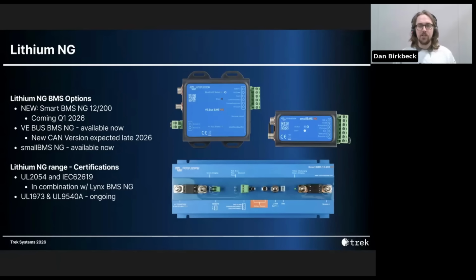The VE.Bus BMS NG and smallBMS NG are available now, with a VE.Bus BMS NG CAN version expected later this year. On the certification side, Victron has achieved both UL 2054 and IEC 62619 certifications for lithium NG batteries when paired with a Lynx BMS NG. The UL 2054 specifically evaluates the battery pack, including its casing and protective circuitry, to reduce the risk of fire or explosion during operation. UL 1973 and UL 9540A certifications are in progress as well, with a few battery models still pending approval.